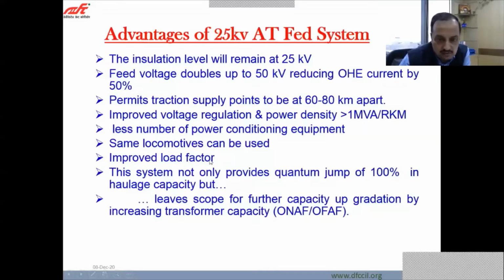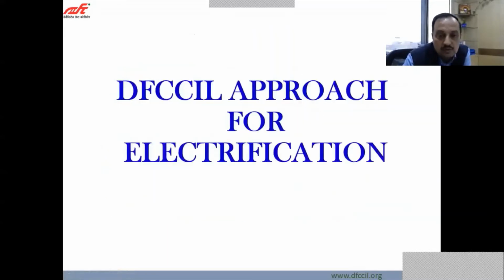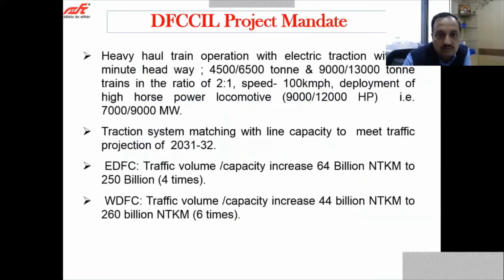Load factor is improved, and the system not only provides a quantum jump of 100% in haulage capacity, but it also leaves scope for further capacity upgradation. So not only are we increasing the capacity by 100%, but there is further scope for capacity upgradation by increasing the transformer capacity, that is, operation of transformers in ONAN, ONAF or OFAF modes. If we operate these transformers that way, the capacity of the system is enhanced again. So what is the DFCCIL approach for electrification?